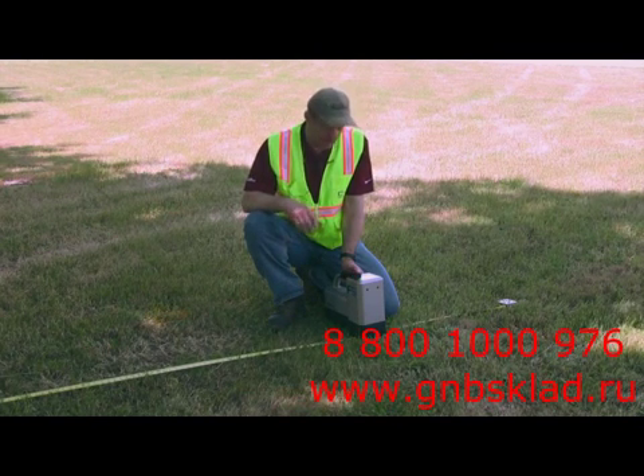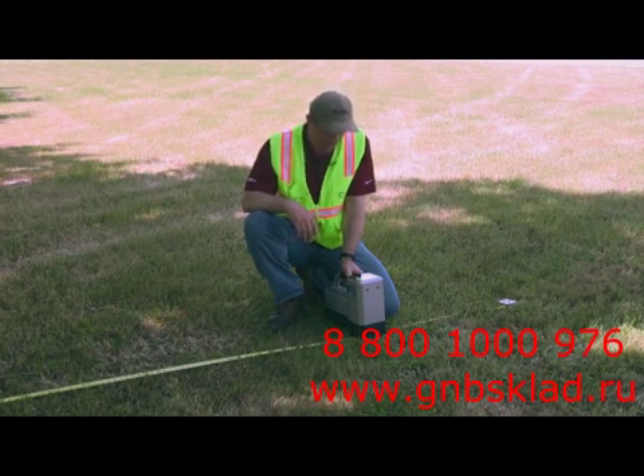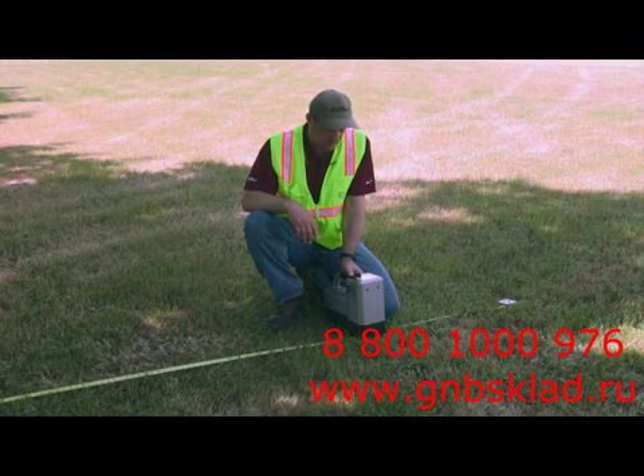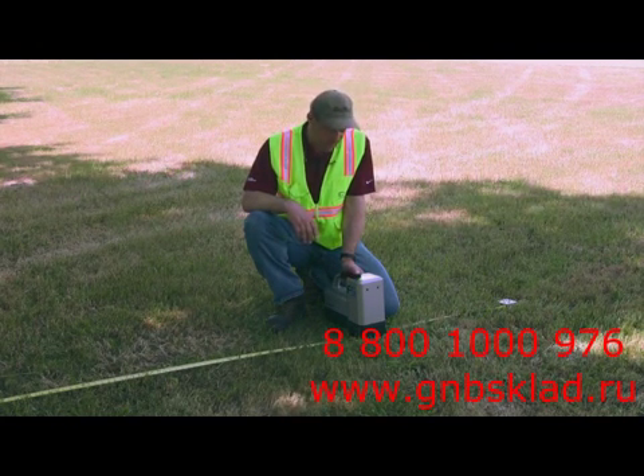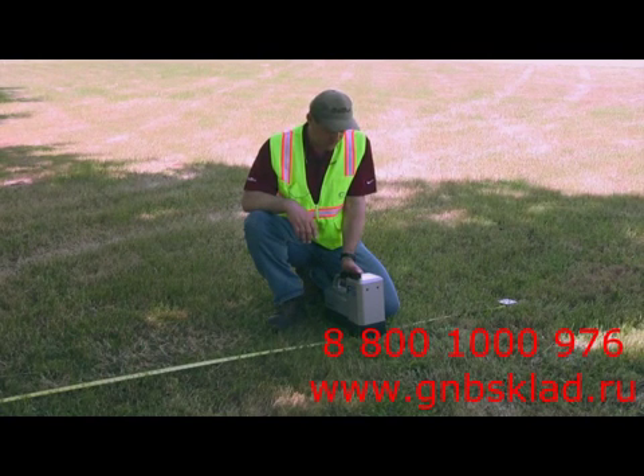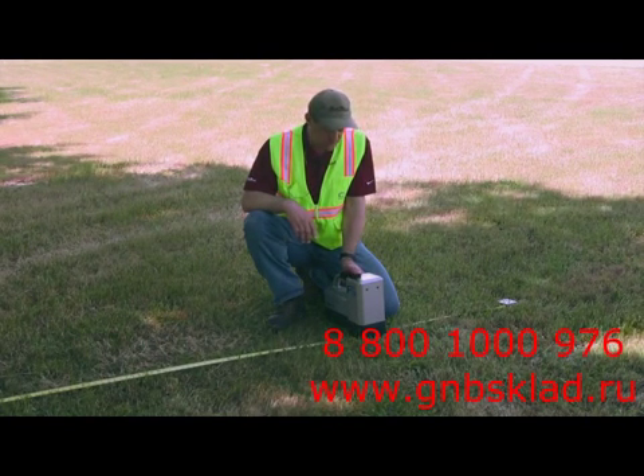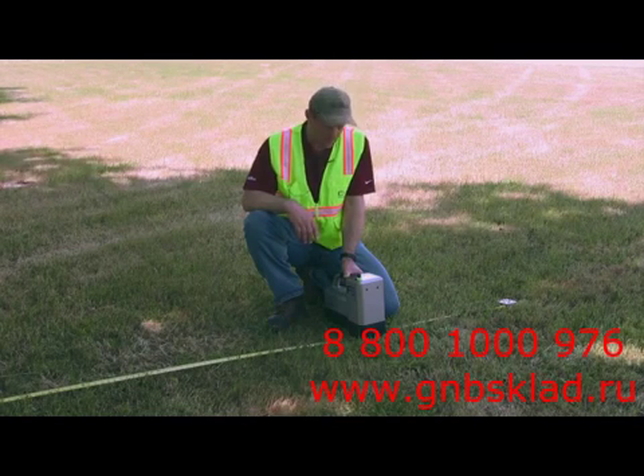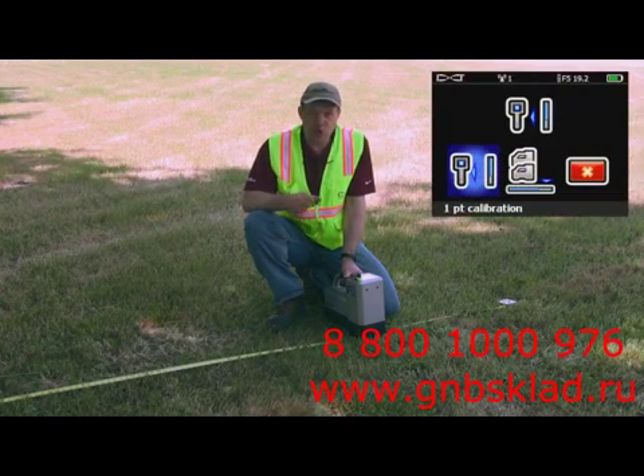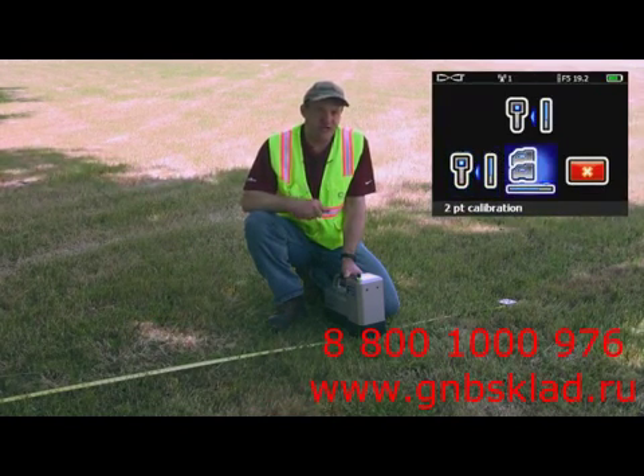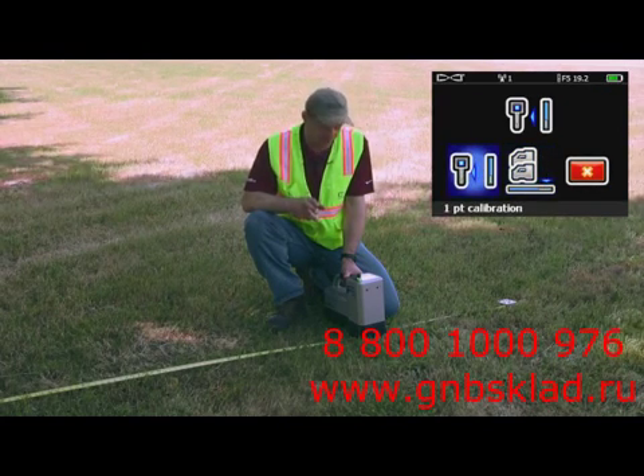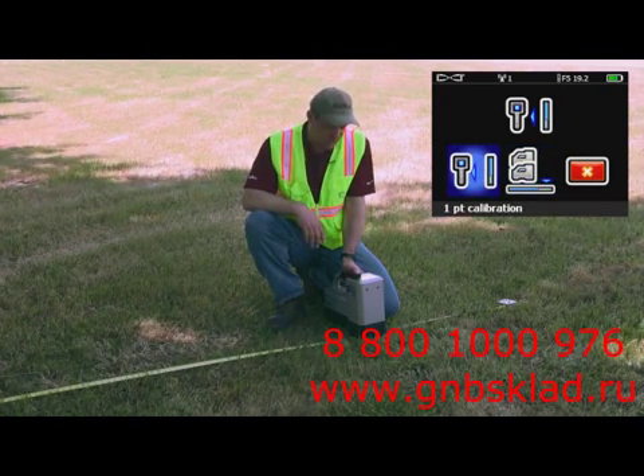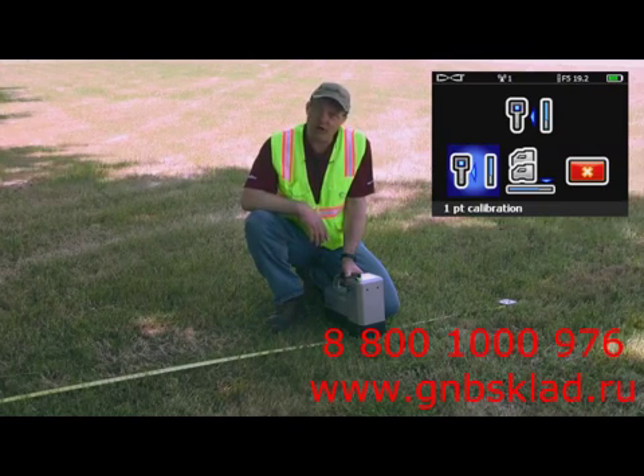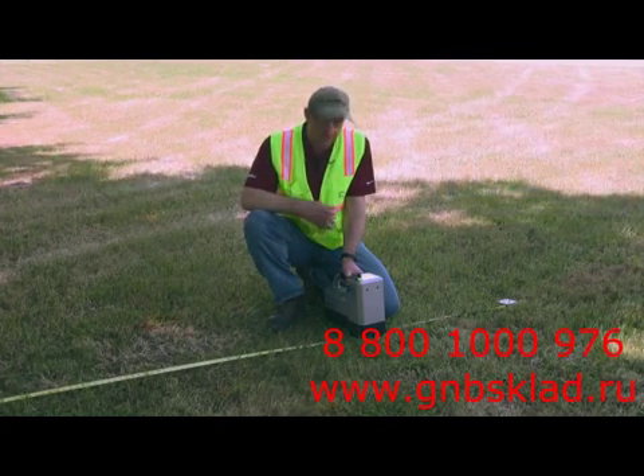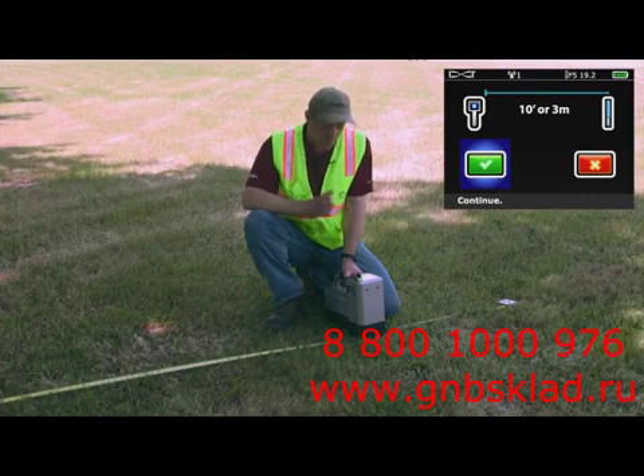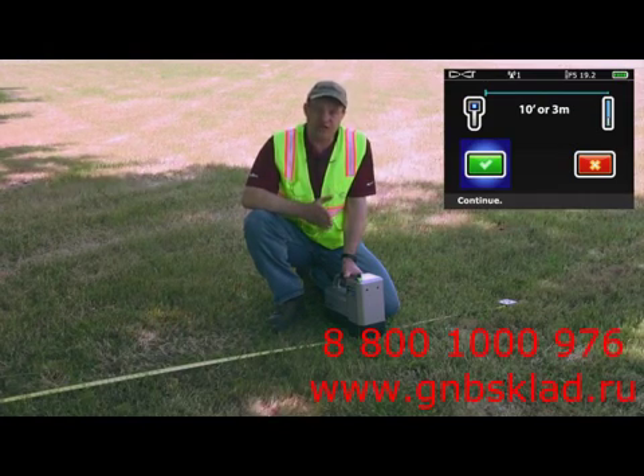Very simply, you go to the calibration menu, click it. You go to the calibration menu, which is right upper right corner of the main menu. Click it. You get two options here. You get a 1-point, 2-point calibration. Always select the 1-point calibration. You highlight it with the thumb switch here. I've now highlighted 1 point. Click it. And now I get a nice icon that really specifies how the orientation should be.